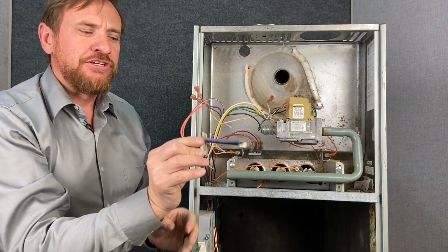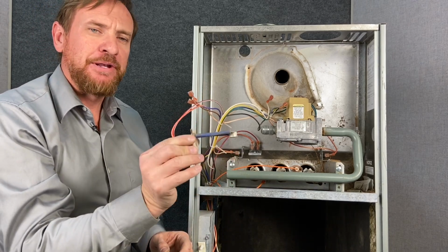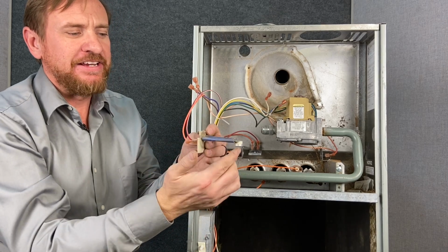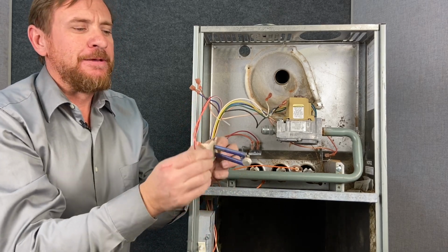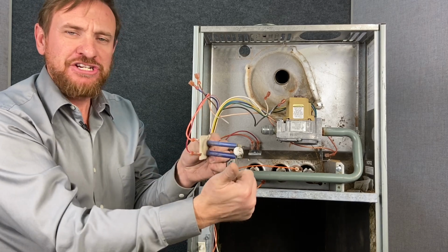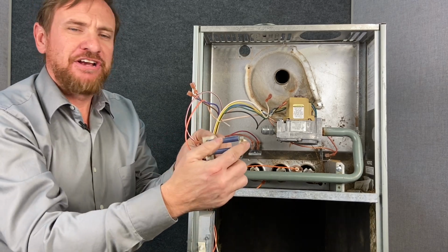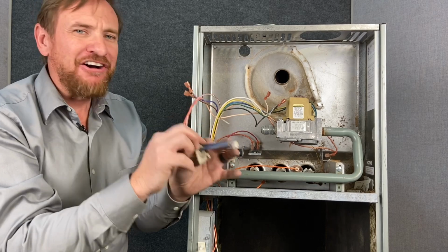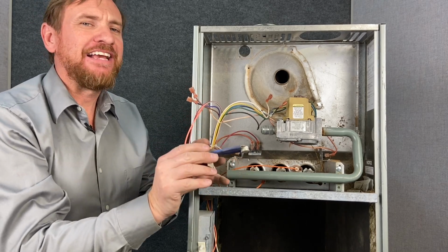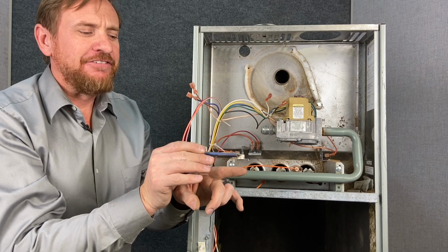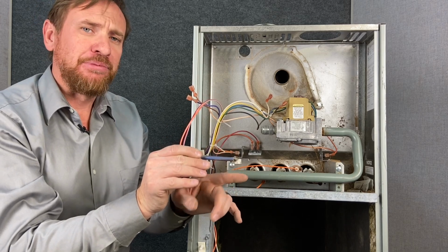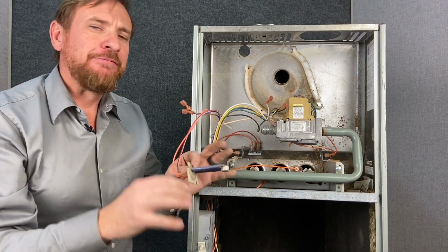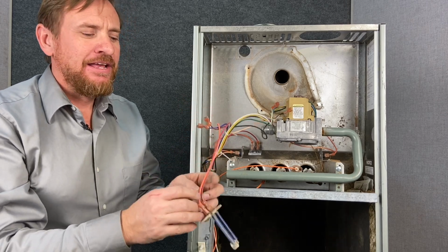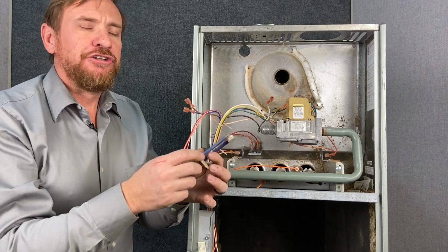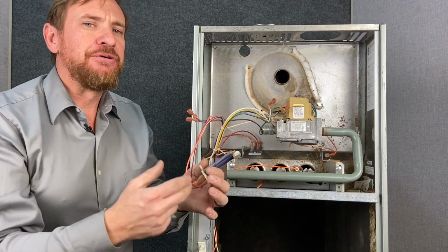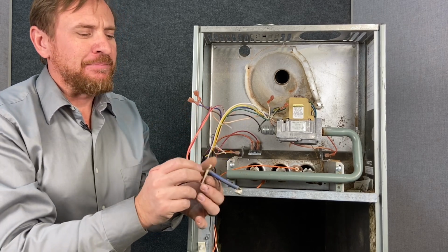Now it's very important that you note how this comes out, because you want to put it back in the same way. If the sensor was facing down, you want the new one facing down. If the old sensor was sideways in this direction, or in this direction, or if it was down, up, however it was, you want it the same way, because the manufacturers have engineered precisely how it goes. Some of them have little fan diverters, a little piece of metal that blocks the airflow. However it came out, you need to be very careful to put it back in that same way, because that could be a cause of what we call a nuisance call for these limits tripping when there's no problem in there. So make sure that goes back precisely how it is.